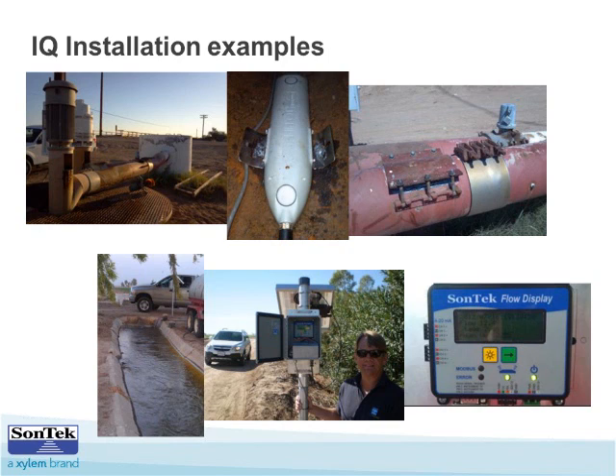The short answer is no, we don't have an ice setting yet. The instrument will still operate. Probably what happens is the water level sensor will still detect water level and continue its calculations, and as long as the IQ itself hasn't iced over, it'll still be operational in water.